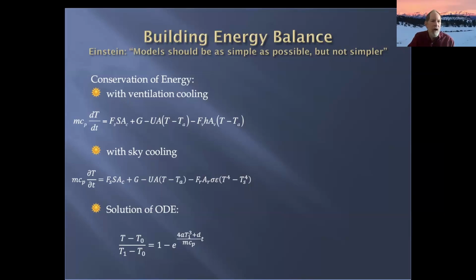For ventilation cooling, on the left-hand side is the thermal capacitance times the time rate of change of temperature. On the right-hand side, the first two terms are the gains: the first is the solar gain, and G is the internal heat gains. The last two terms are the losses: the envelope losses and the ventilation cooling losses. We have a similar equation where just the last term changes for sky cooling. It gets more complicated because temperature is to the fourth power, but both equations have analytical solutions, allowing us to get a result very quickly for hourly temperature.